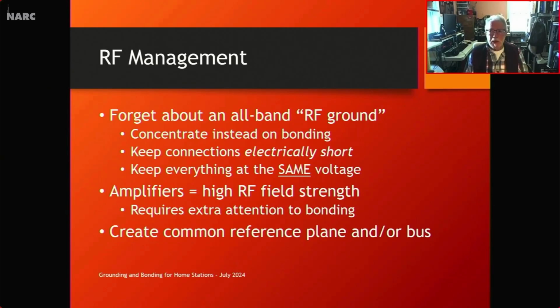So concentrate on doing a good job of bonding, connecting everything together. Keep your connections electrically short, even at the higher frequencies, so that the ground connections themselves don't start acting like an antenna or a transmission line. The idea is to keep everything at the same voltage no matter the frequency. Keeping things at the same voltage, so they go up and down together, means the current does not flow between pieces of equipment. That's what you want to minimize.